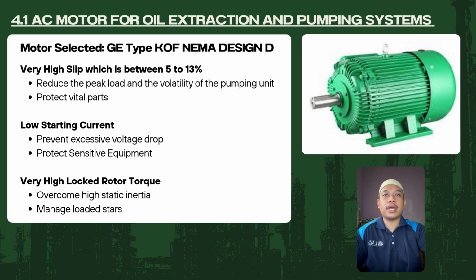Lastly, this motor has a very high locked rotor torque. Both operations require this feature to overcome the massive physical resistance of starting heavily loaded machinery from a complete stop in this location, including high static inertia. It also manages loaded starts. The motor must immediately lift the weight of the entire column of oil in the well as soon as it starts turning. Next is the motor ratings.